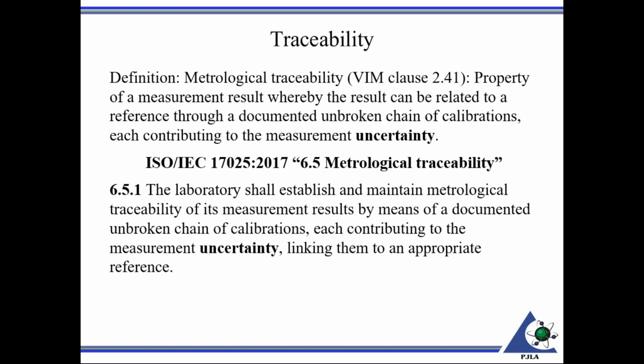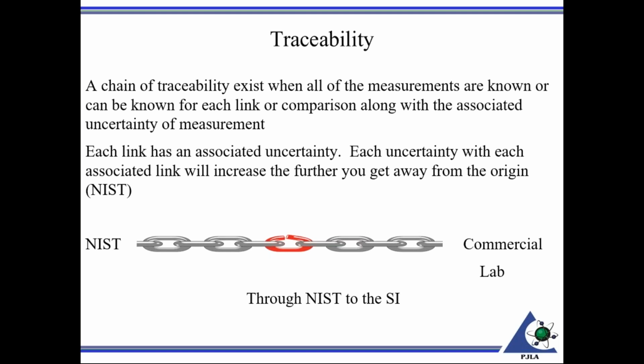So we have a clause, we see uncertainty associated there, and we also see the requirement in 17025 concerning metrological traceability. The laboratory shall establish and maintain metrological traceability of its measurement results by means of an unbroken chain of calibration, each contributing to the measurement uncertainty, linking them to an appropriate reference. Hence, if you're looking at a report that states its measurements are traceable, by definition, that includes the measurement uncertainty. So a chain of traceability exists when all the measurements are known, and can be known, for each link of the comparison, along with the associated uncertainty of the measurement.